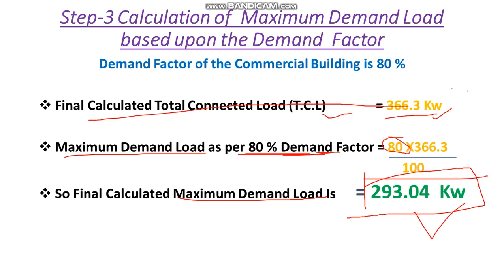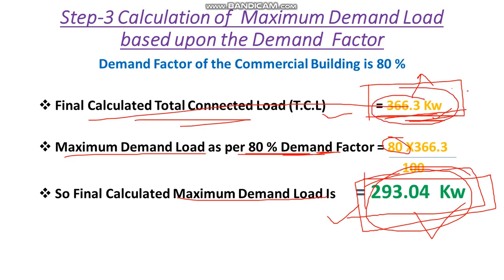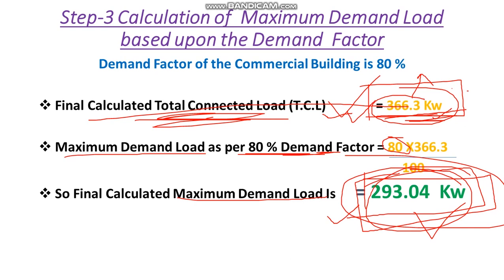This 293.04 kW is our final calculated maximum demand load. If we were to calculate the transformer size based on the total connected load of 366.3 kW instead, the transformer would be oversized compared to actual demand, which would be a waste of money.